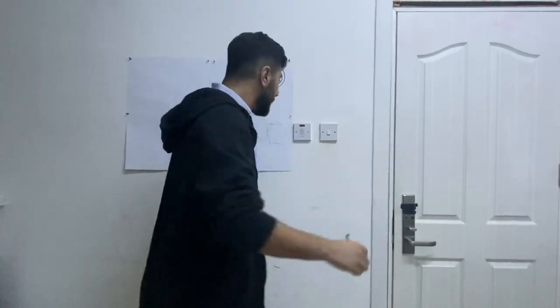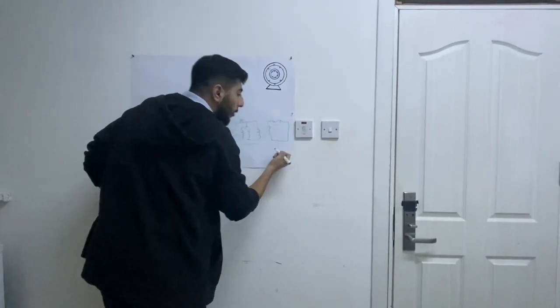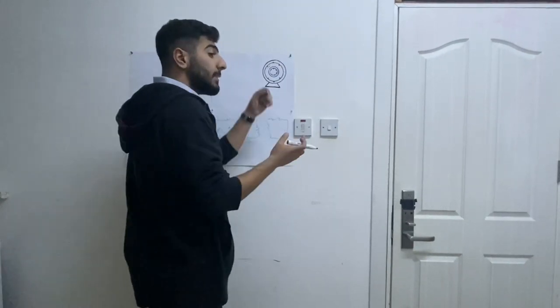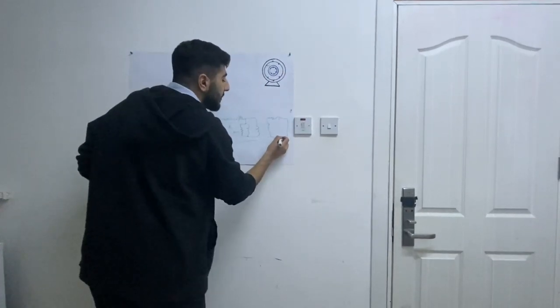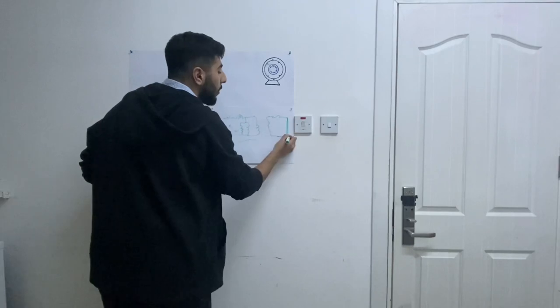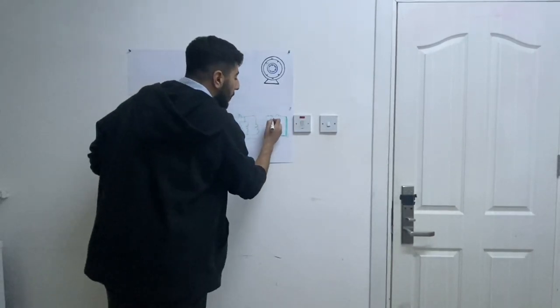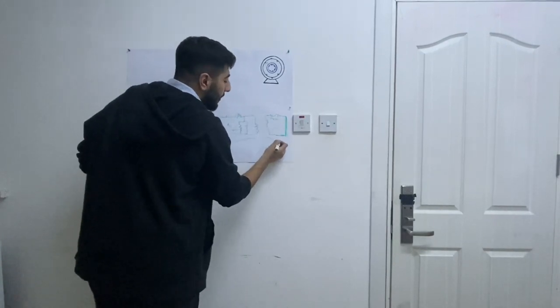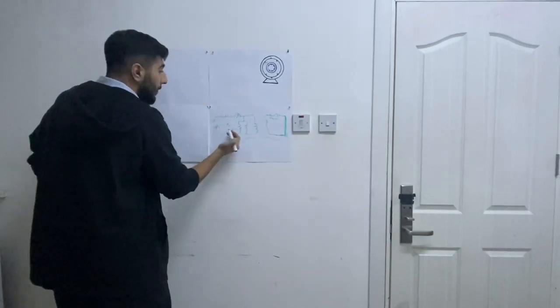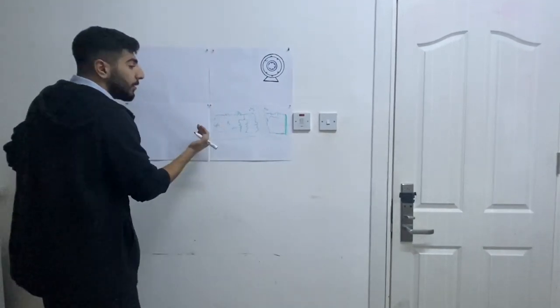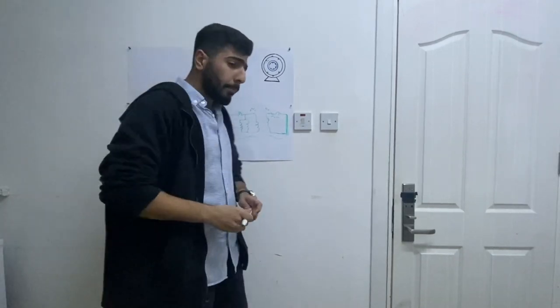Here is where the induction motor differs from a transformer: the rotor circuit is closed — short-circuited — and this is important. That is the main difference between an induction motor and a transformer. Otherwise, similar to a transformer, we can refer the rotor circuit elements to the stator side by multiplying by the turns ratio, moving them to the primary side of the circuit.